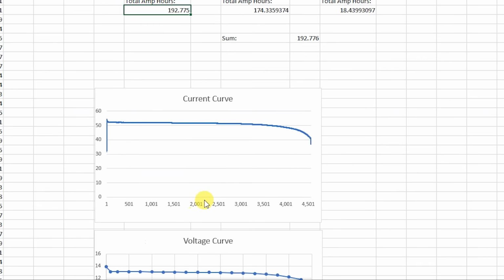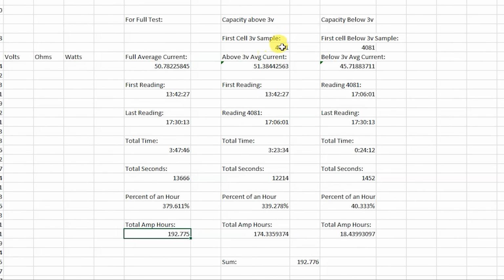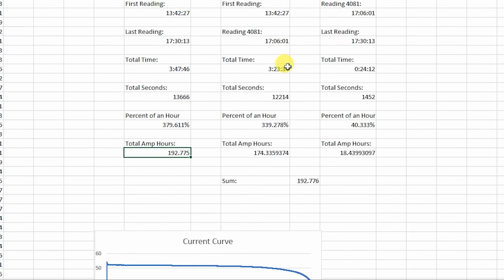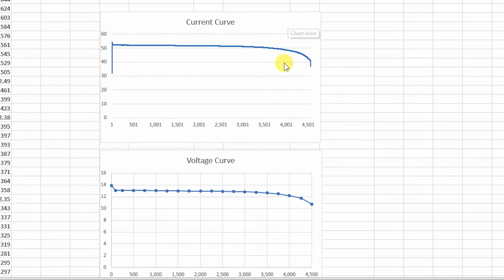Keeping in mind, let's look at sample 4081 because this is very interesting. If we look at the graph, this is in the 4,000 sample range, a little past here, and if you line these up vertically they're about the same. This is where you really start seeing the decline in the curve. You can imagine that if I pushed these harder below that 2.5 volt reading, it's very little compared to how flat the curve is on the other part of the test.